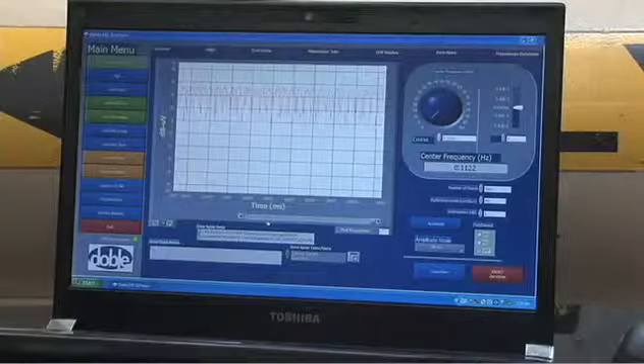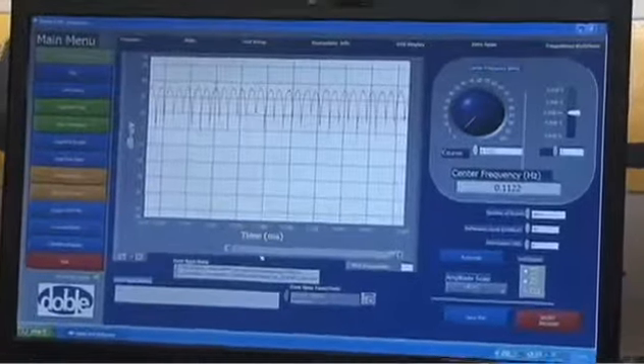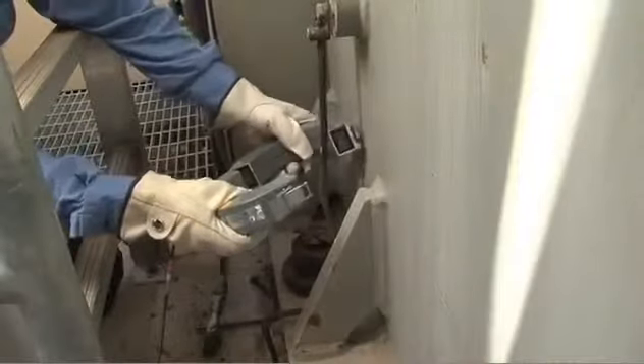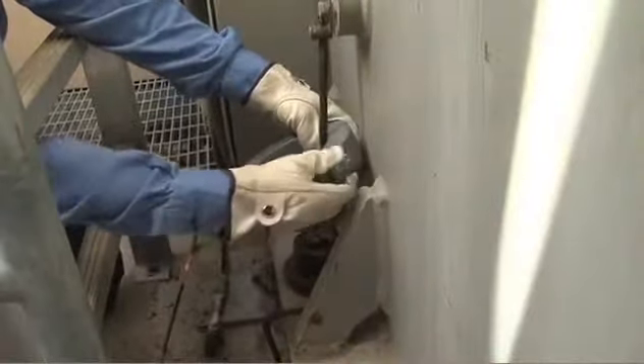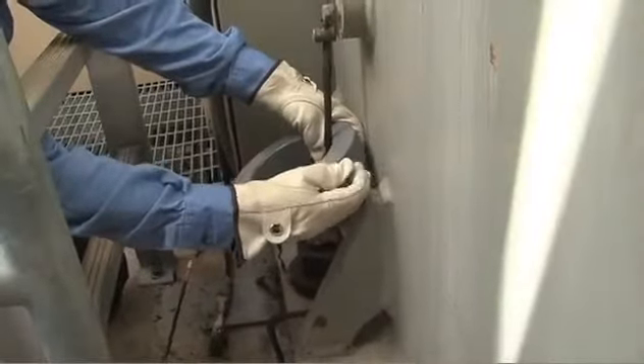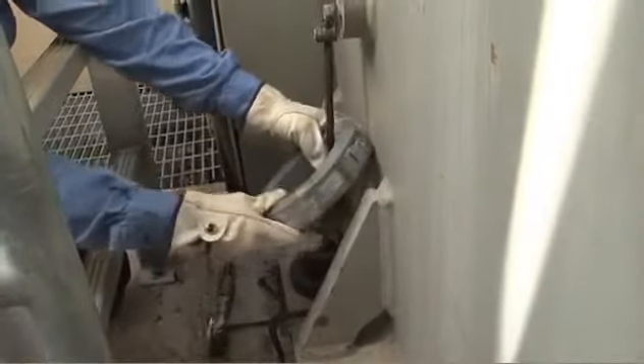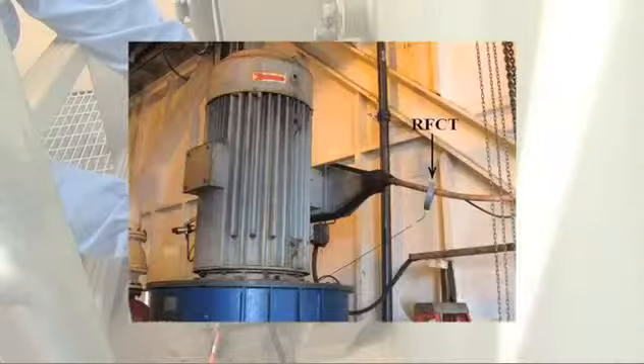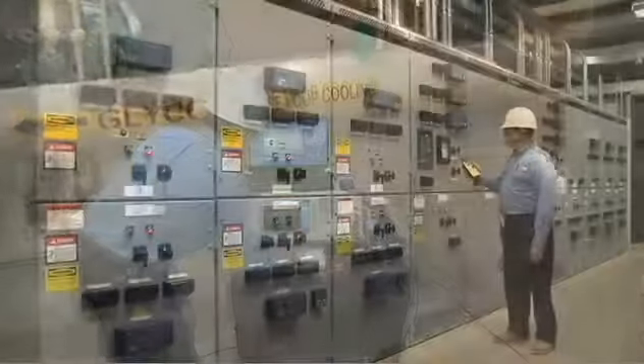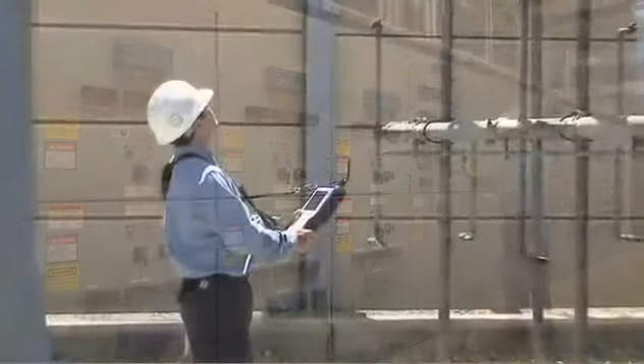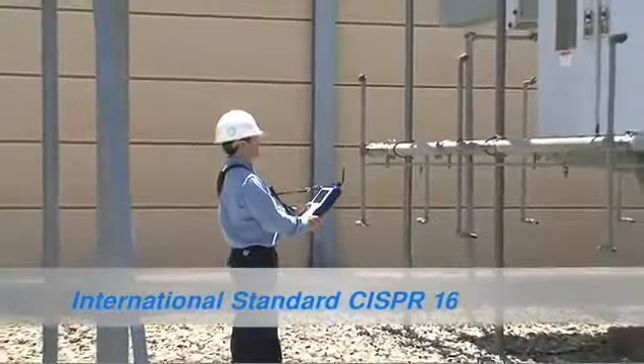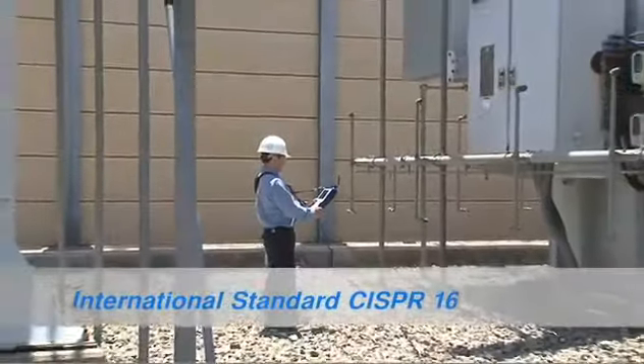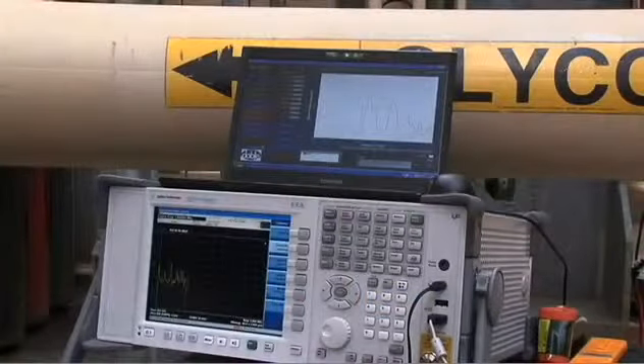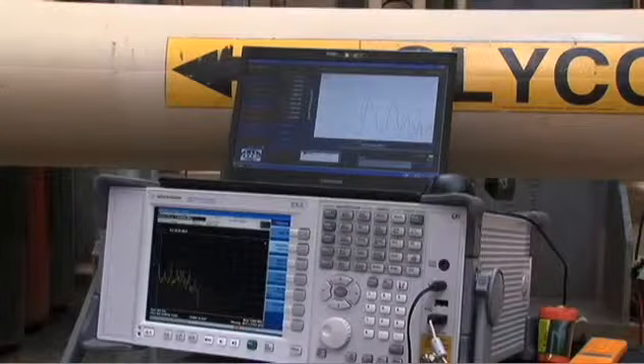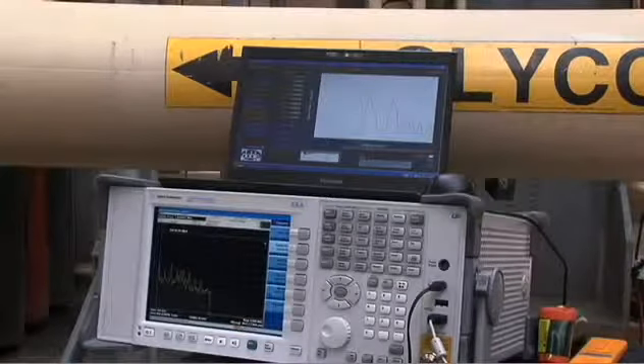and arcing at defects. EMI data is collected from the temporary placement of a split-core radio frequency current transformer around the power conduit, safety ground, or neutral lead of the component being tested. No hot connection is required to any energized conductor, or hardware installation modifications. EMI data collection follows the international standard CISPR 16. The test equipment is very sensitive and measurement accuracy is traceable to national standards.